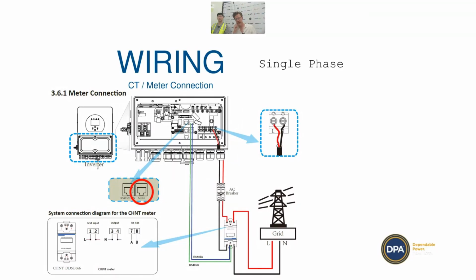I've had people looking at the settings, and I haven't seen any so far that didn't have the settings correct right out of the box, so you shouldn't have to adjust the baud rate and things like that. I did have someone get a different size CT and have to change the CT ratio on the meter afterward, which was a bit of a headache. I'd recommend not doing that unless you really have to, but it can be done.